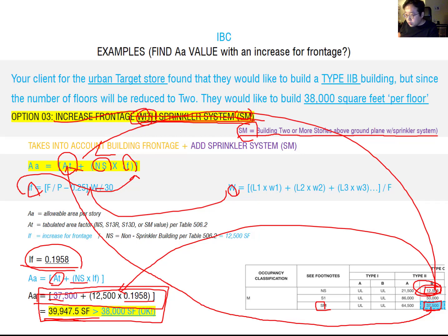Okay. So on Tuesday and Thursday, we talked about the IBC concept, and the 5 basic considerations for the IBC. We also discussed occupancy and construction type, and using construction type and occupancy, how you can find the exterior wall fire minimum rating hours from the neighbor building, right? And also you can find the maximum allowable floor area, height, and story from the building occupancy and construction type.